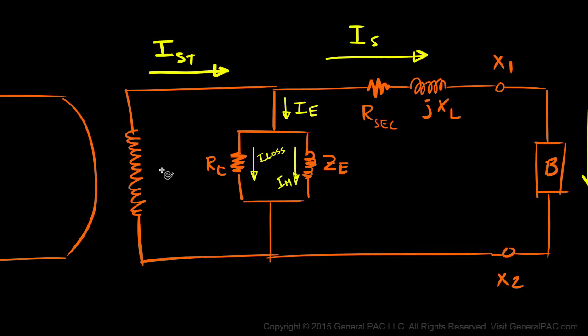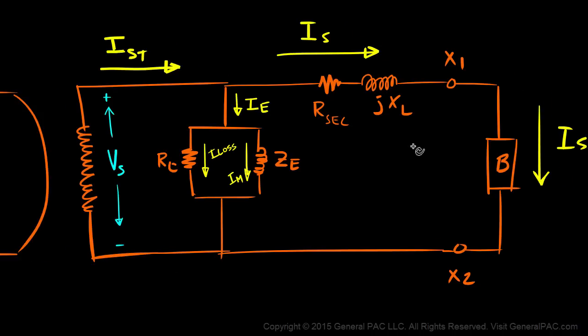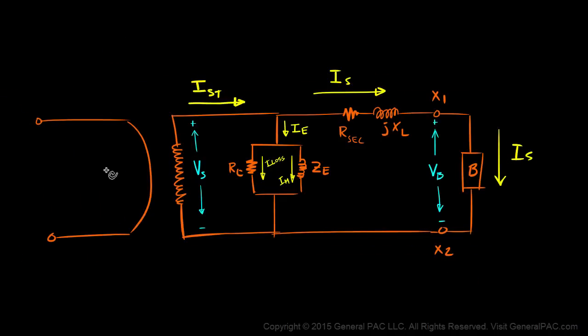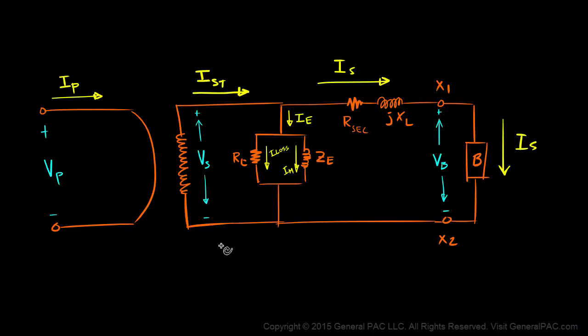For our voltages, we're going to call this voltage VS, which is measured across the winding. We're going to call this VB, which is measured across the two secondary terminals. And of course we have the primary voltage, which is measured across the primary winding. Notice how we have a single turn on the primary side, and of course we also have the primary current. This is the simplified CT model that we're going to analyze in Part 6.